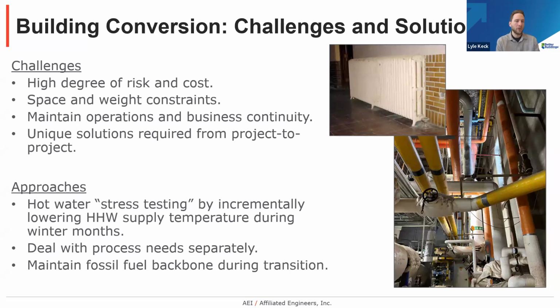Very often it is not a copy and paste type of effort from project to project or building to building. So some approaches for mitigating a few of those challenges include a very common practice called hot water stress testing. This is where you incrementally lower the heating hot water supply temperature during a cold snap or winter months and see how low you can still maintain the current operations and space conditions. So you might start with 180 and take it down in 5 or 10 degree increments and see what happens. You may find out that, for example, you only need to replace the air handling unit coils instead of every terminal coil in the building.